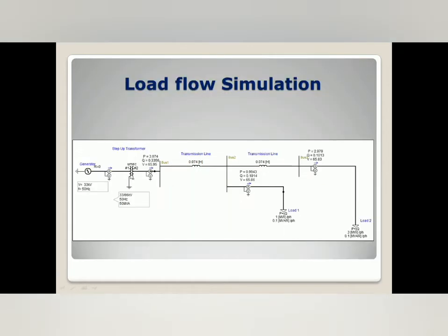To accomplish the load flow simulation, the electrical meter instrument needs to be configured to get the data from the simulation. The multimeter shows that the sending power from the transformer is nearly equal to the received power at the end of the load. The meter proves that the 33/66 kV, 50 MVA transformer setting is enough for the load to receive the power. Some of the difference in reactive power and voltage values is because of the losses and the effect of the transmission line. In this simulation, the length of the transmission line is assumed to be 80 km for each section.